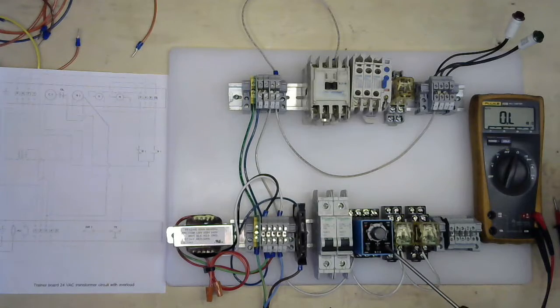We are using a 120 volt time delay relay. This is a 120 volt delay on make and delay on break. This is two 120 volt double pole, double throw relays we're using. These are spare terminal blocks because in motor controls we do not use wire nuts for connection points. So these are spare terminal blocks should we need them for future diagrams and wiring that we'll be doing.